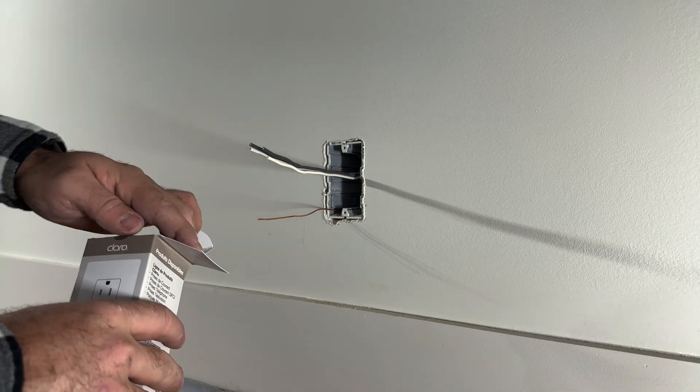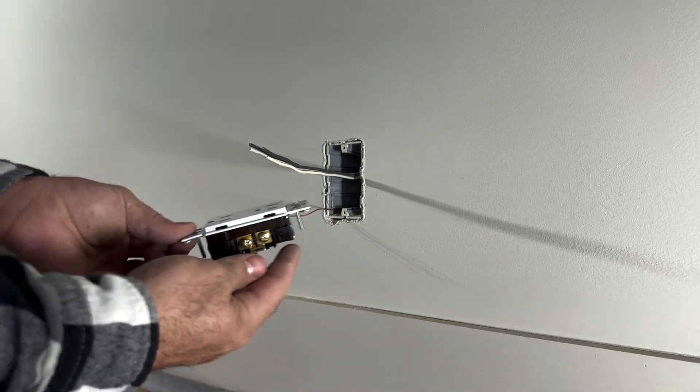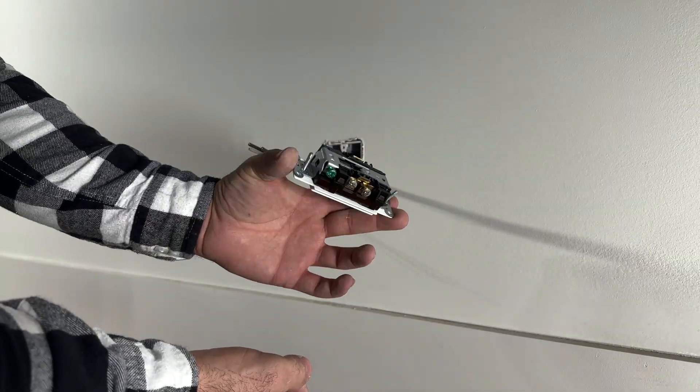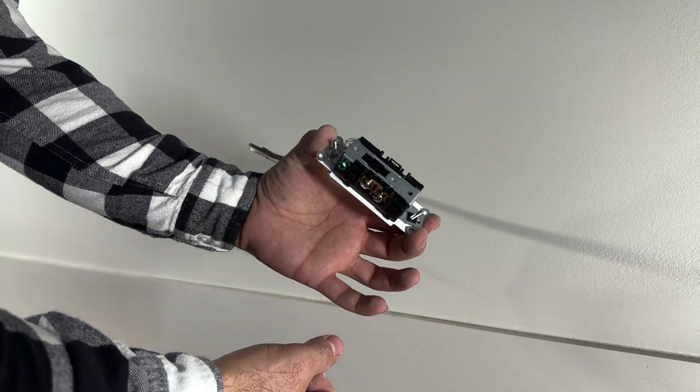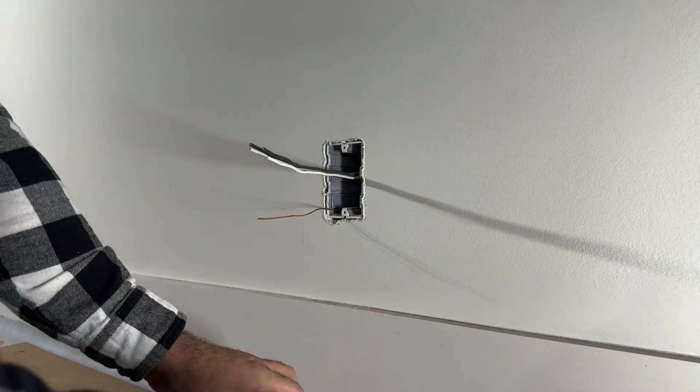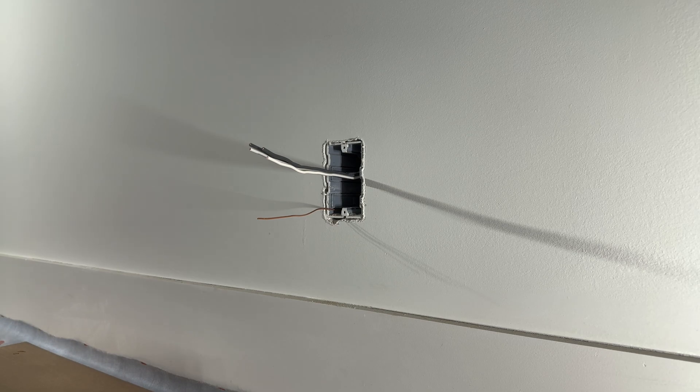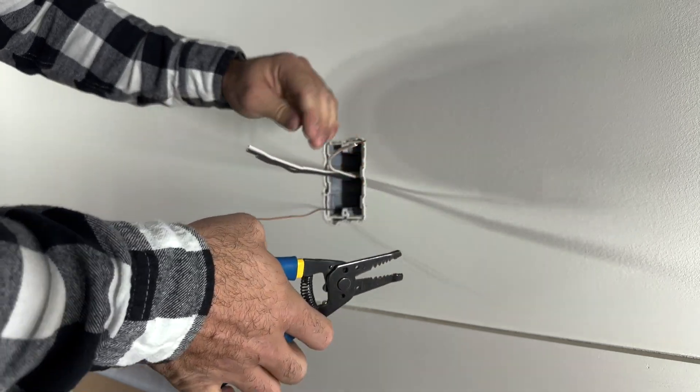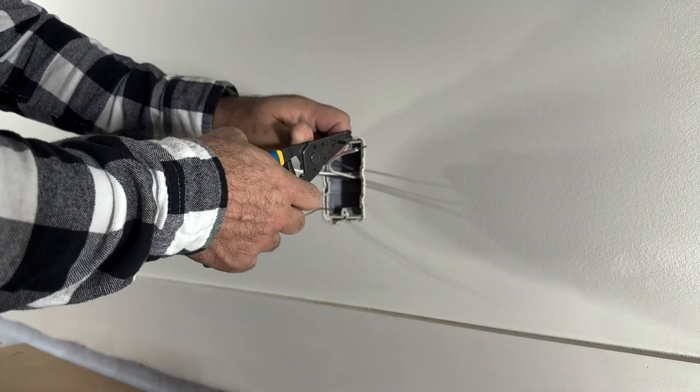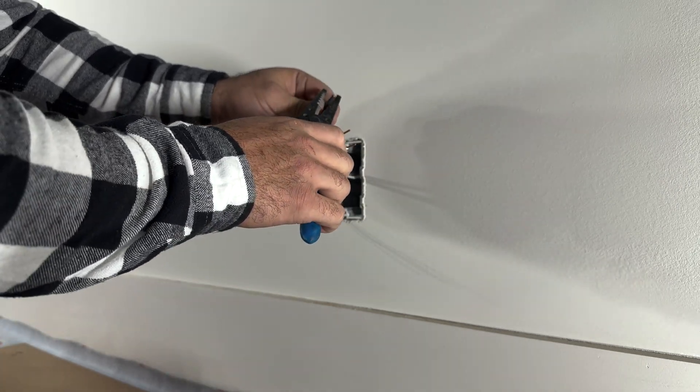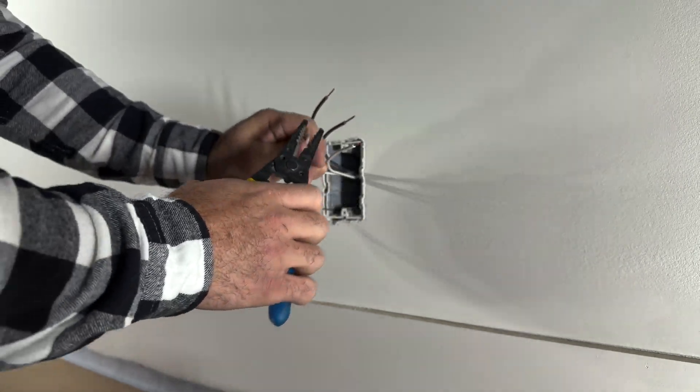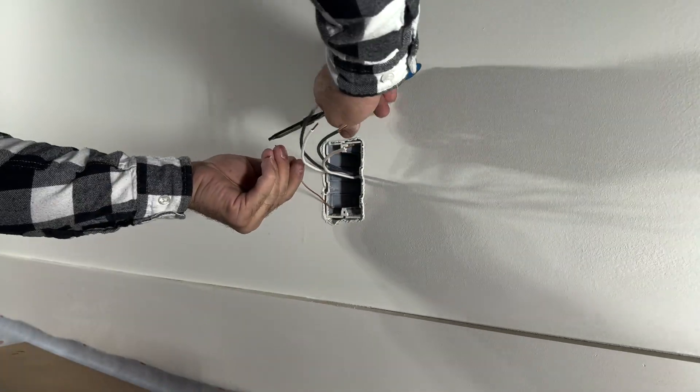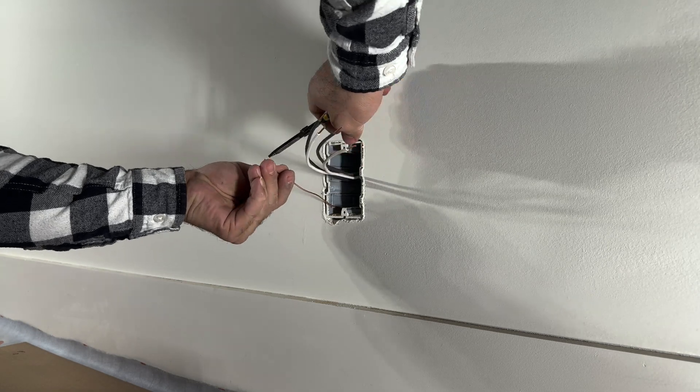We will follow by unboxing the receptacle. Here we are. This receptacle is quite nice to use because it has terminals where you can put your conductors in. Now we can strip our conductors. I usually do about three-eighths to half an inch. And we will do a small loop on the ground wire.